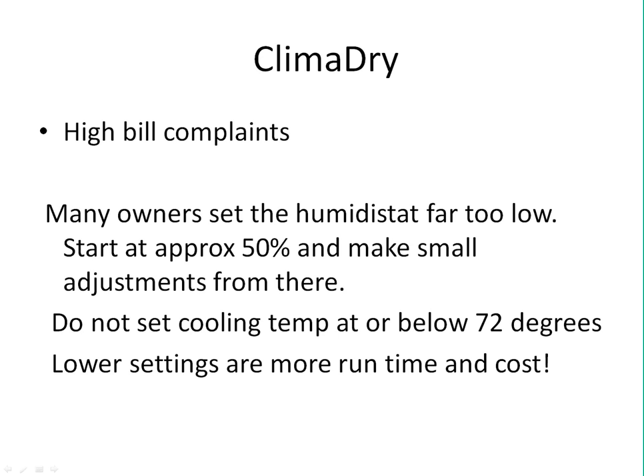Now I'm going to cover a little bit of the ClimaDry. ClimaDry was our whole house dehumidification, not so much out in the Northwest, certainly something that we see down the South and Midwest, a little up in the Northeast where they have higher temperatures and more humidity. One of the common issues and complaints that we get is, you know, this thing is really delivering a high bill. And most of the time we find this is the cause. The owners typically have set the humidity level too low. In other words, they're trying to drive it too dry.